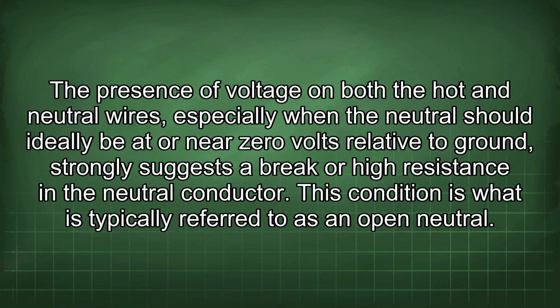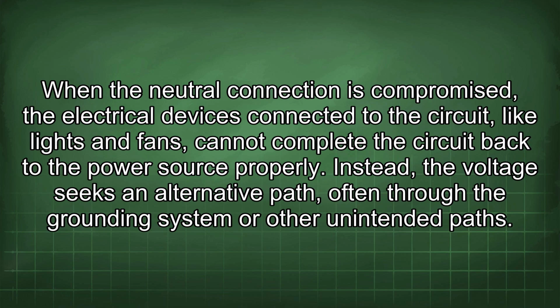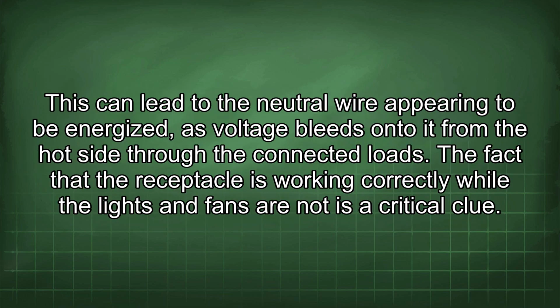The presence of voltage on both the hot and neutral wires, especially when the neutral should ideally be at or near 0 volts relative to ground, strongly suggests a break or high resistance in the neutral conductor. This condition is what is typically referred to as an open neutral. When the neutral connection is compromised, the electrical devices connected to the circuit, like lights and fans, cannot complete the circuit back to the power source properly. Instead, the voltage seeks an alternative path, often through the grounding system or other unintended paths.